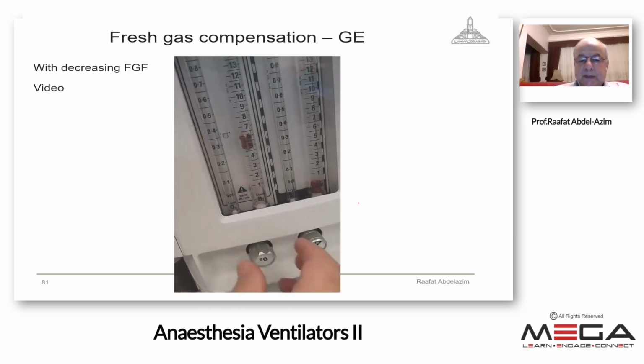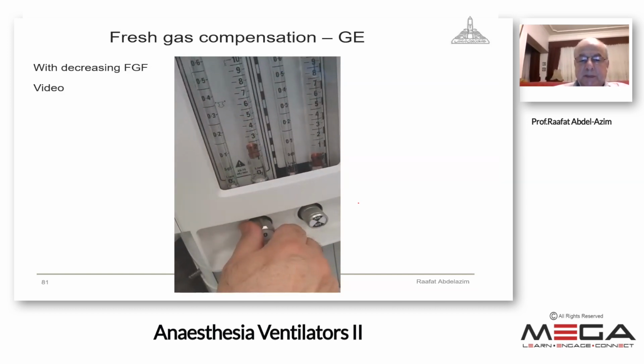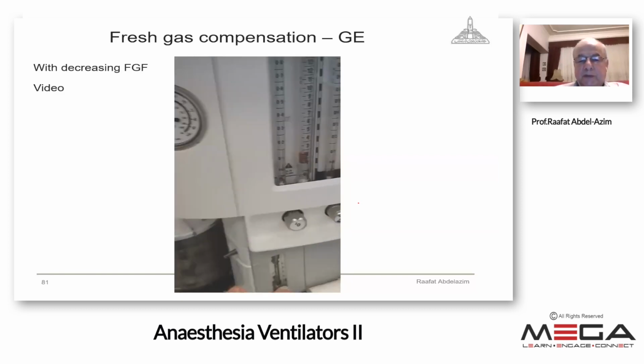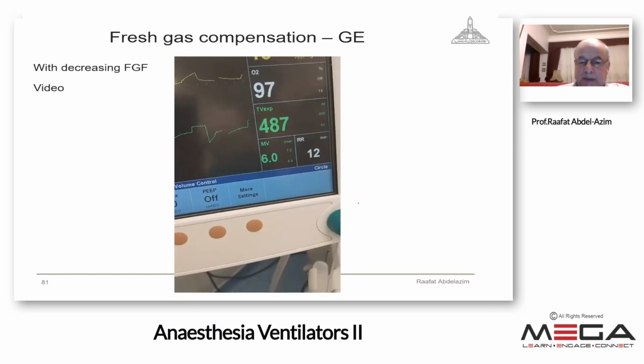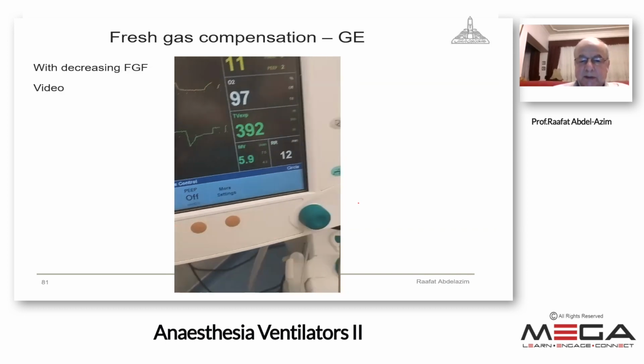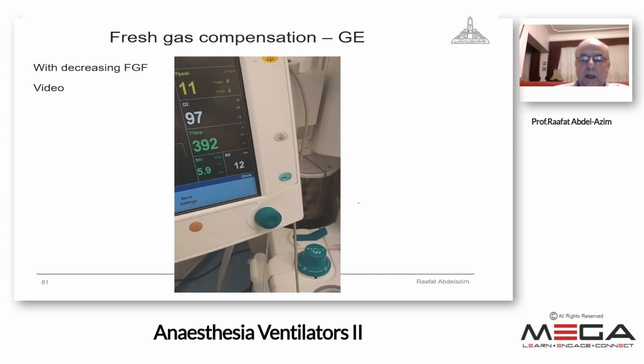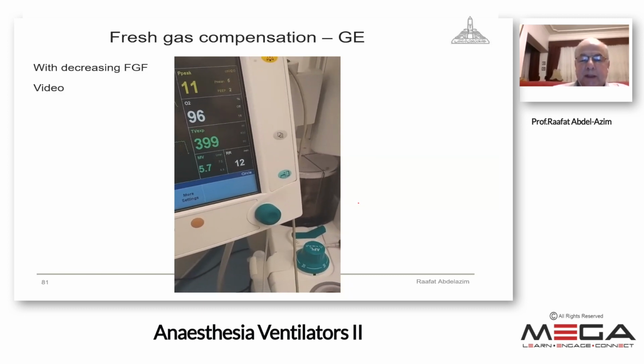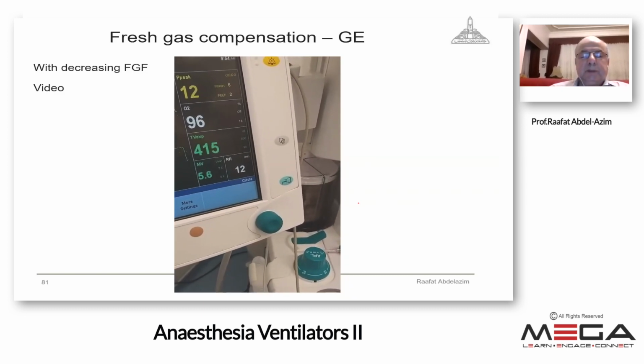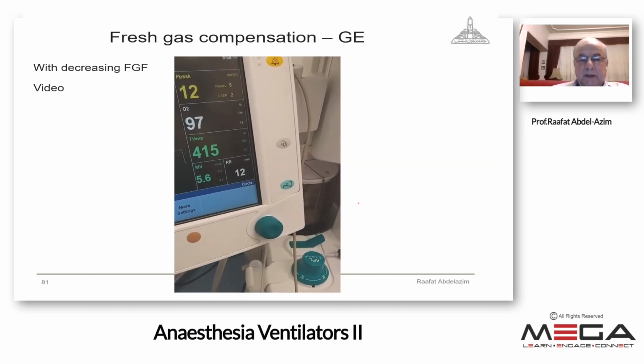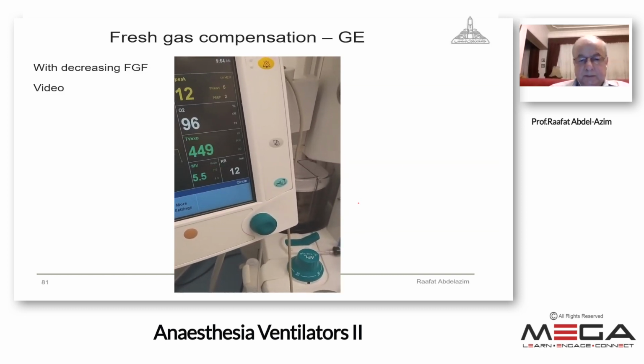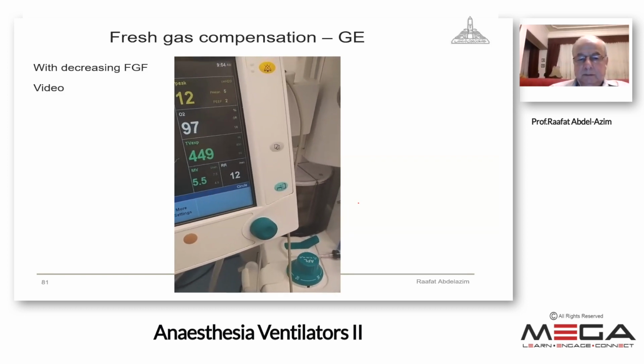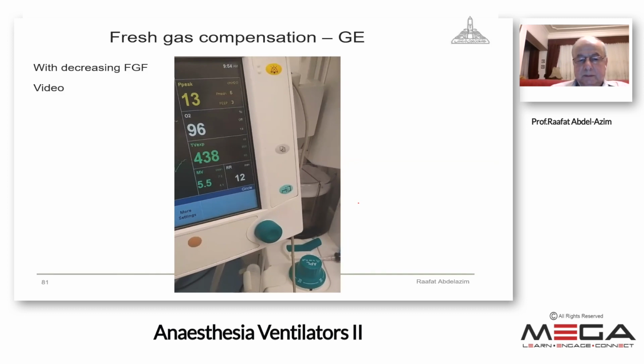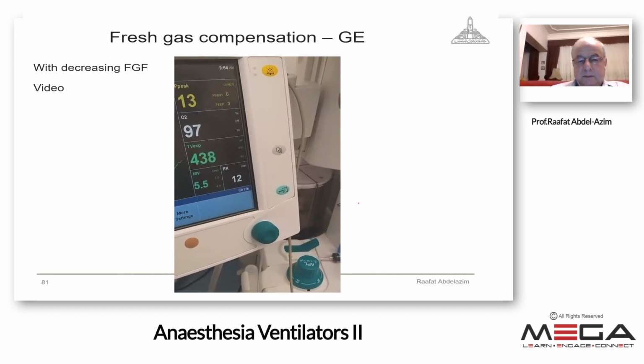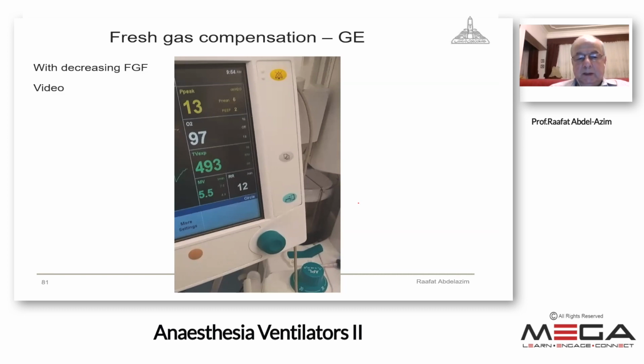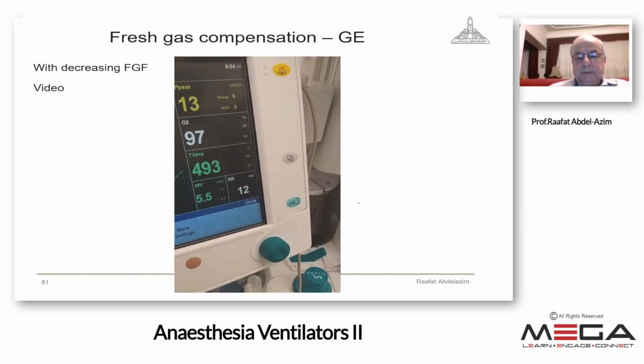If we decrease it from 6 liters to 2 liters, this means that the effect of fresh gas flow will go down. The delivered tidal volume will decrease because of the decrease in the fresh gas flow. But the fresh gas compensation will push it up again to be close to the preset tidal volume. This is fresh gas compensation. Again, it is here near the preset.